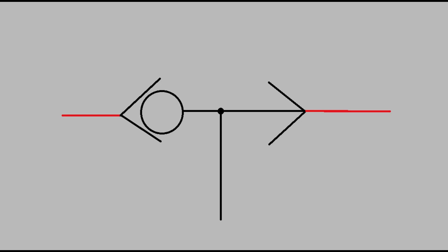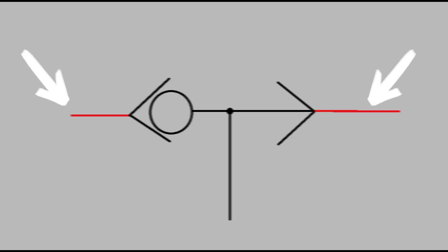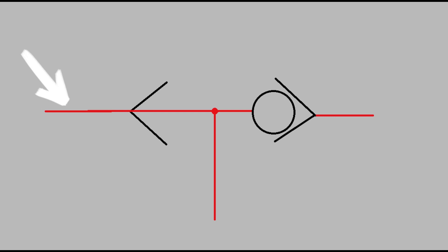A shuttle valve receives two pressure signals. These signals work against each other with the higher pressure signal winning out and moving a check valve over to allow the higher pressure signal to pass through the output.